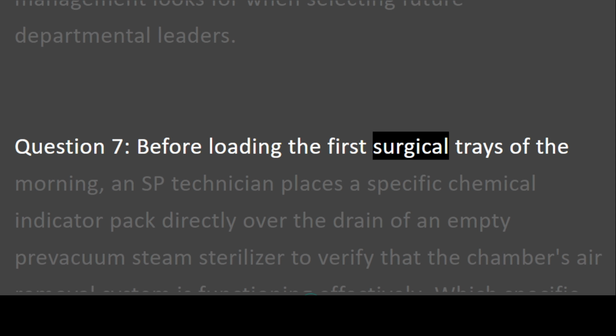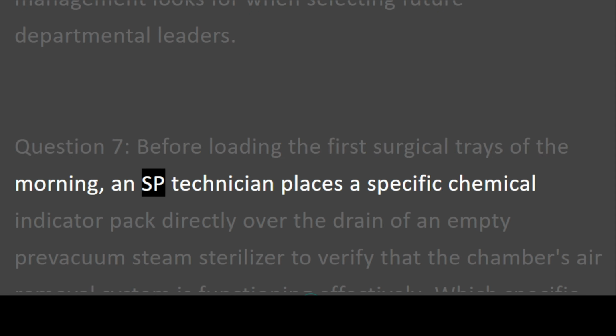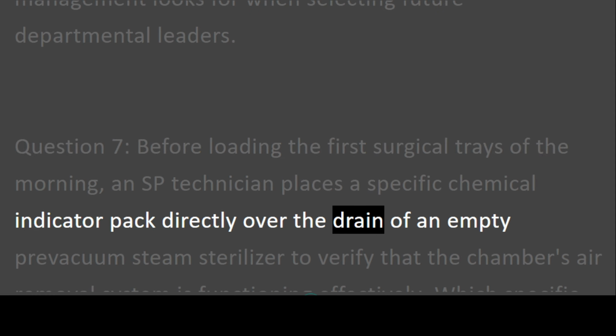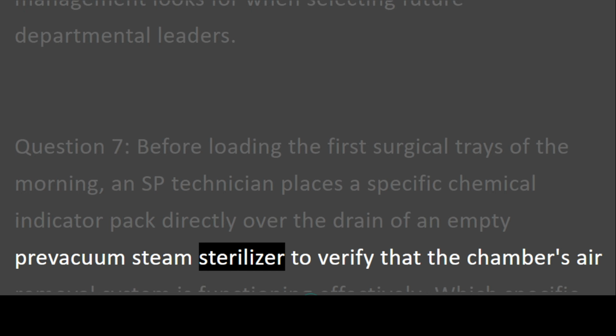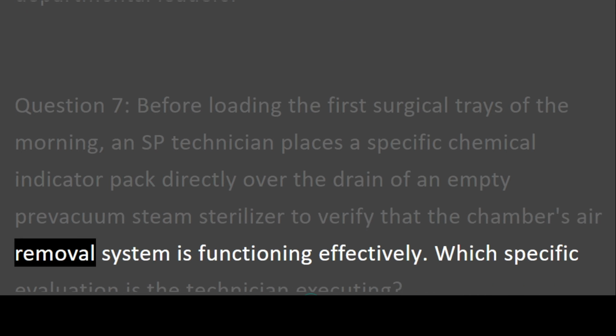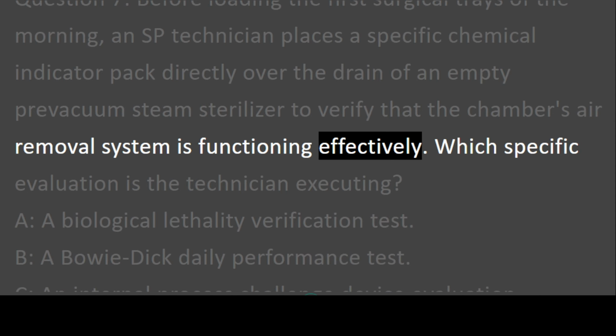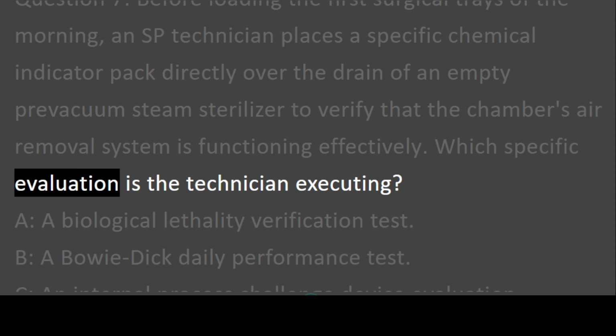Before loading the first surgical trays of the morning, an SP technician places a specific chemical indicator pack directly over the drain of an empty pre-vacuum steam sterilizer to verify that the chamber's air removal system is functioning effectively. Which specific evaluation is the technician executing?